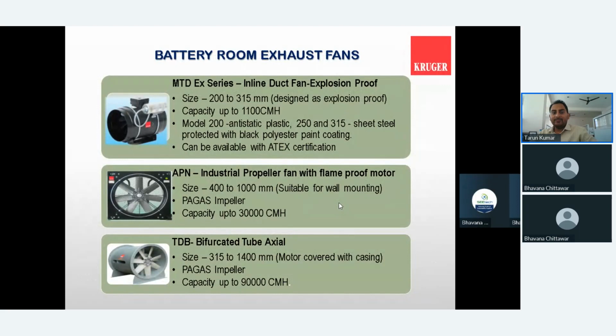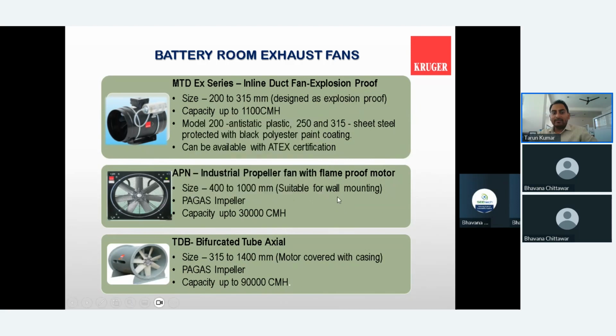Here again we have a fan with a flameproof motor. It is available as an inline fan, as a propeller fan, as well as a bifurcated tube axial fan. In the bifurcated fan, our main purpose is that the motor is bifurcated from the airflow path. In the APN series fan, that is the propeller fan, we put a brass ring with either a bagasse impeller and brass ring. Mainly the purpose is just to segregate the rotating and stationary parts. They should not have any contact, or if they do come in contact, one part will be non-ferrous. For that reason, no spark will be generated.